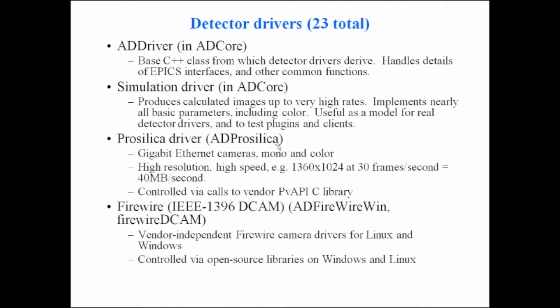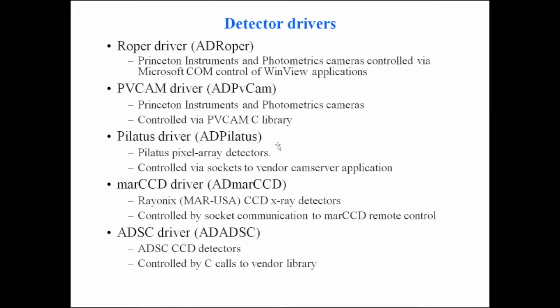There's a Roper driver for Princeton Instruments and Photometrics cameras — an example of controlling a vendor application. Princeton Instruments provides an application called WinView that can be automated by the Microsoft COM (Component Object Model) mechanism. You can also control almost all the same cameras with the PVCam driver, which instead goes through a vendor C library called PVCam. In principle that should work on Linux.